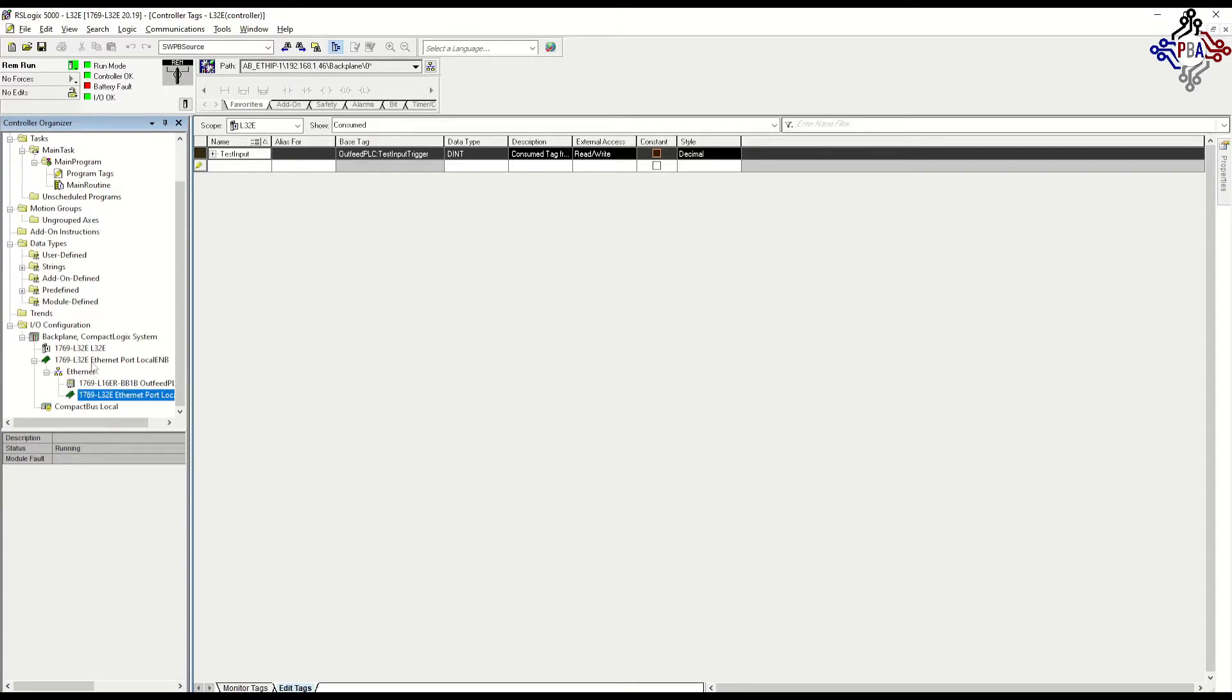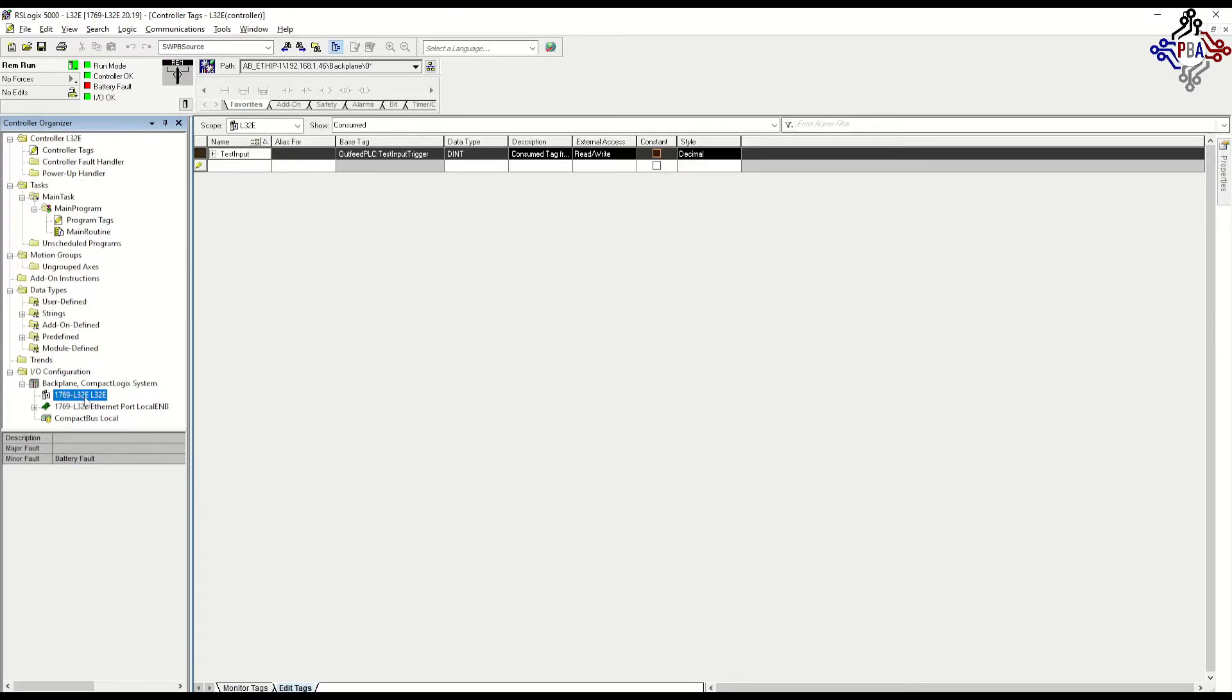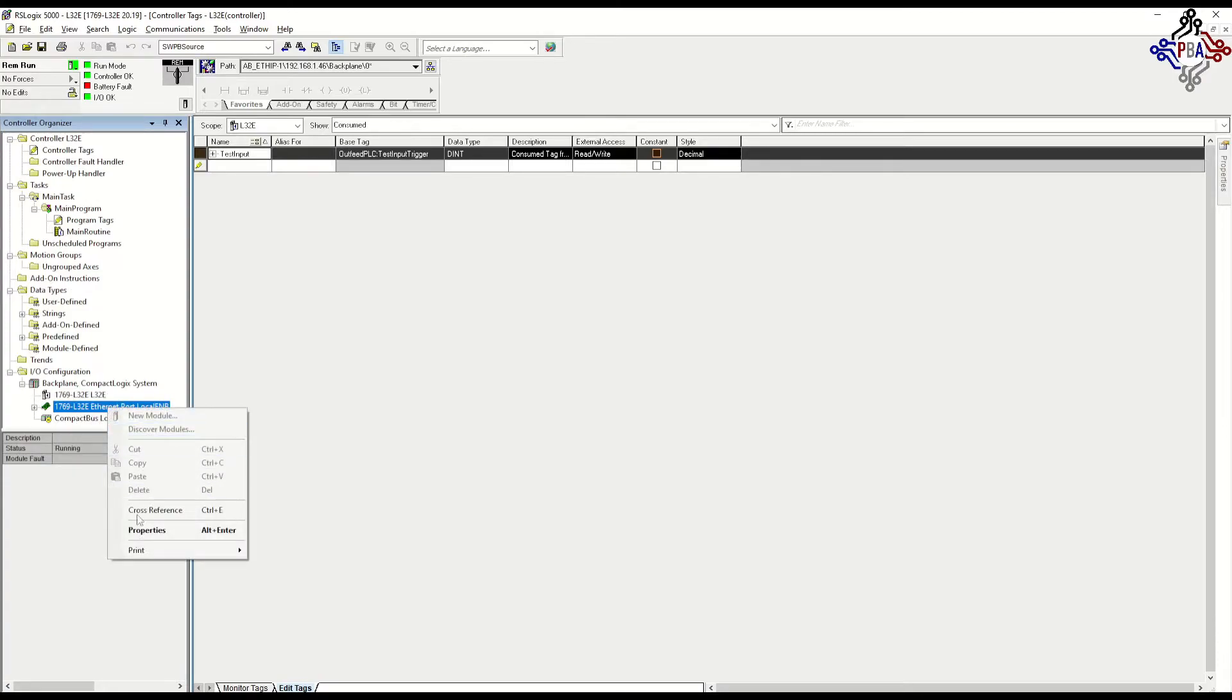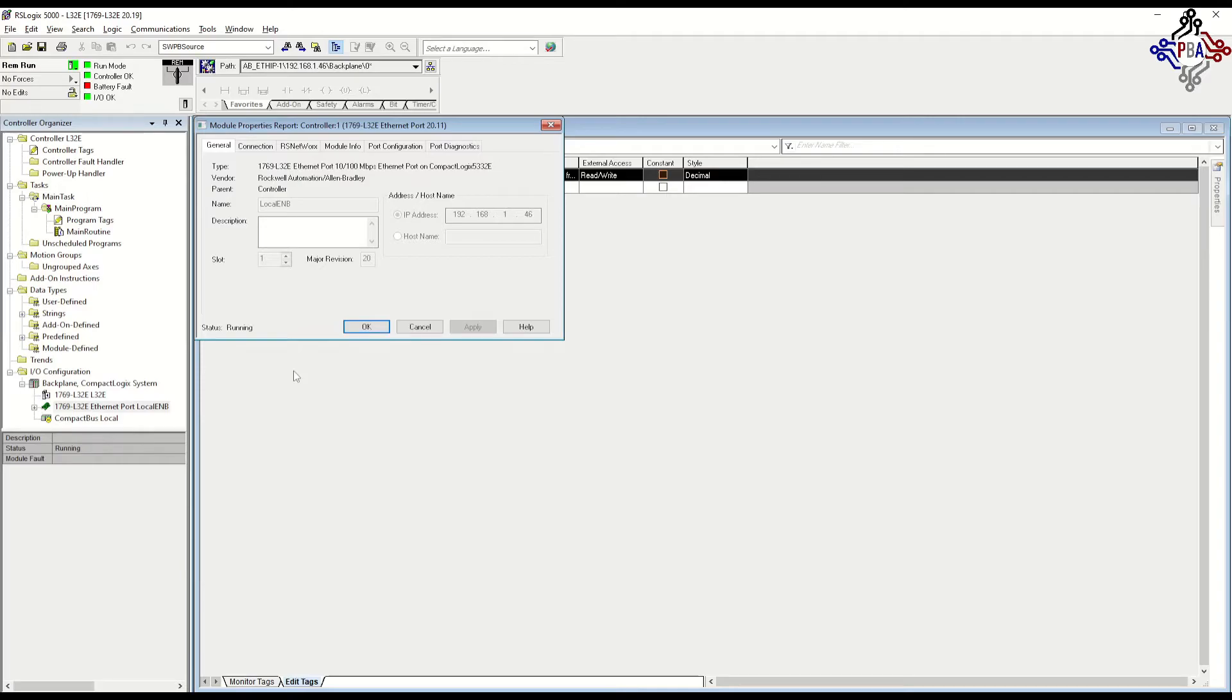The L32E has different modules in different places than you would normally assume. The controller is in slot 0. The Ethernet card, however, if we look at this, is actually slot 1, and then it moves on to the CompactLogix bus. So the first card that you put on is actually in slot number 2.